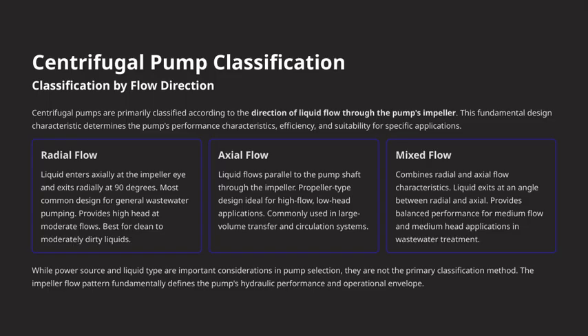Next, axial flow pumps. Here, the liquid flows parallel to the pump shaft, moving straight through the impeller, kind of like a propeller. These are ideal when you need a high flow rate, but at a low head. Think of large volume transfer or circulation systems. They're often used in applications where volume is more critical than pressure.